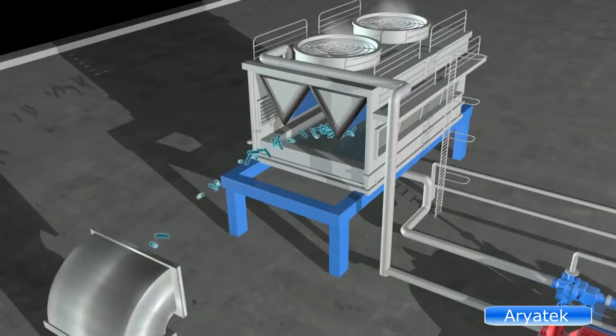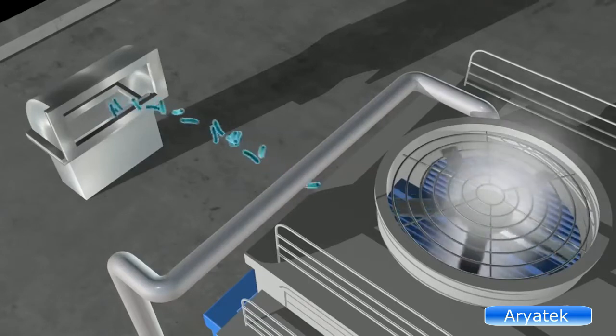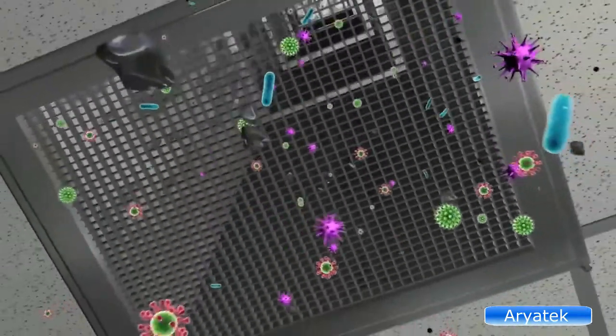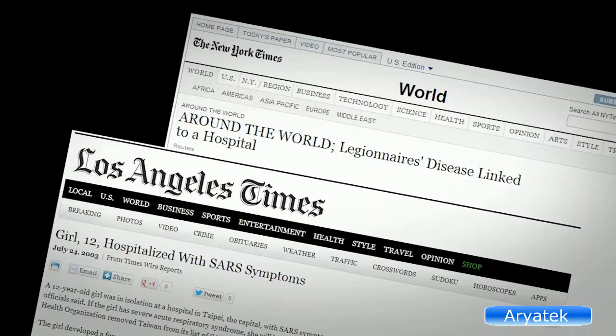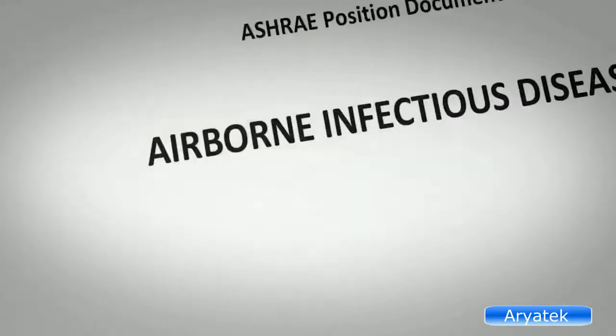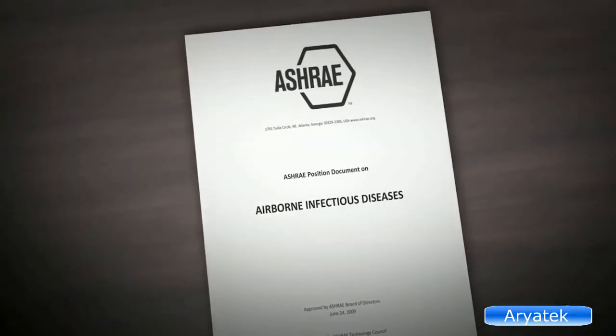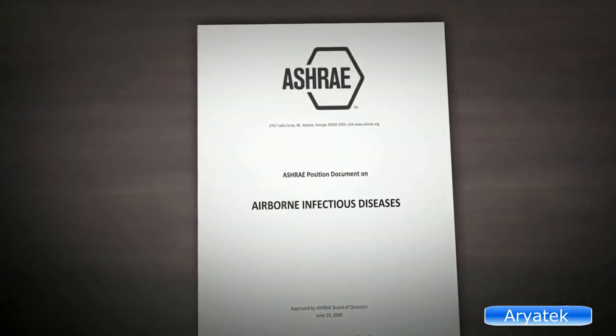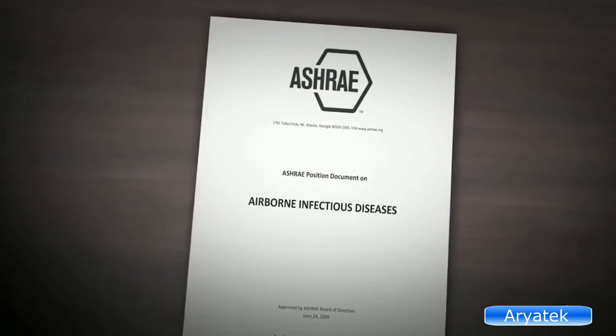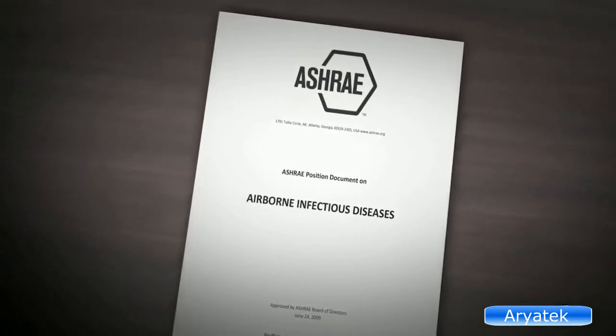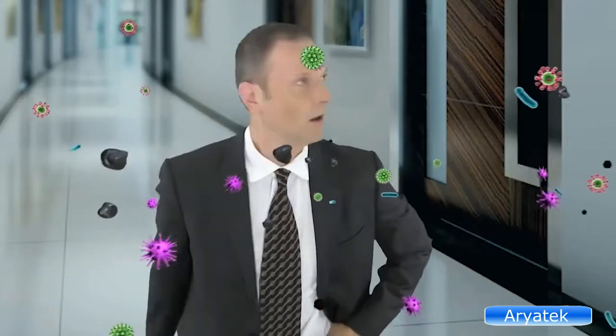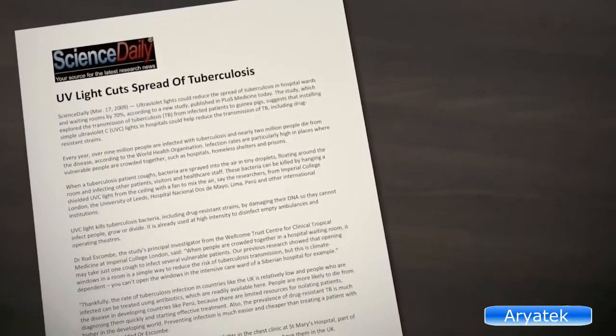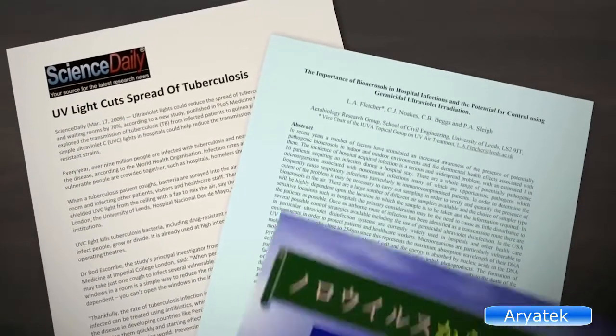Historically, we have felt protected because of the misunderstanding that viruses and bacteria are not distributed through the ducts. Legionella and SARS destroyed this myth. On June 24, 2009, ASHRAE's Board of Directors issued a position document indicating that the AC system distributes viruses. This has been confirmed by medical studies, including a recent one for norovirus.